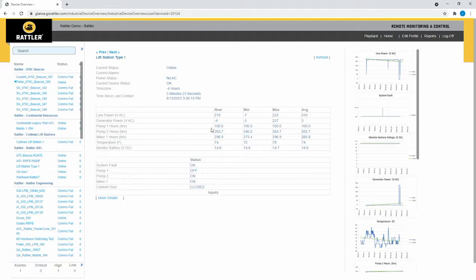Interestingly enough, what we've added for lift stations and industrial monitoring is our remote hour meters. These are really important for maintenance and knowing the status of equipment, because service intervals are done on hours. Pump 1 increments when pump 1 is on, pump 2 increments when pump 2 is on, and so forth, and the mixer likewise.